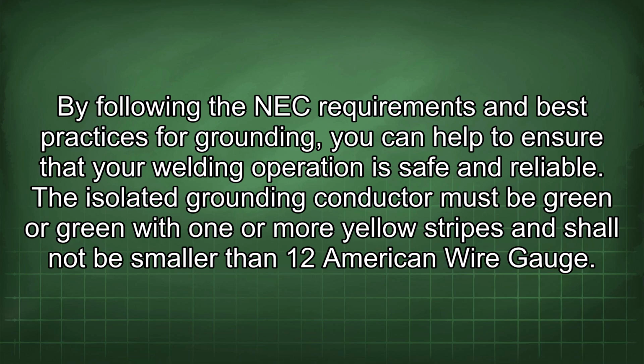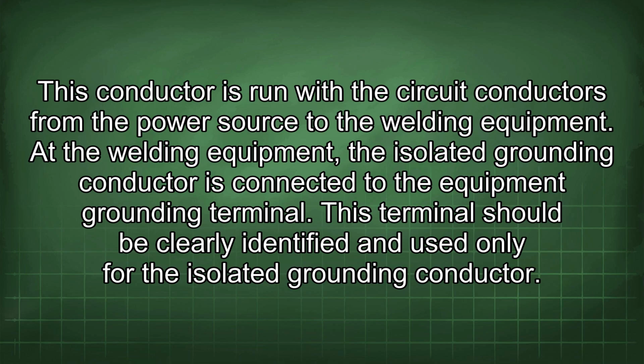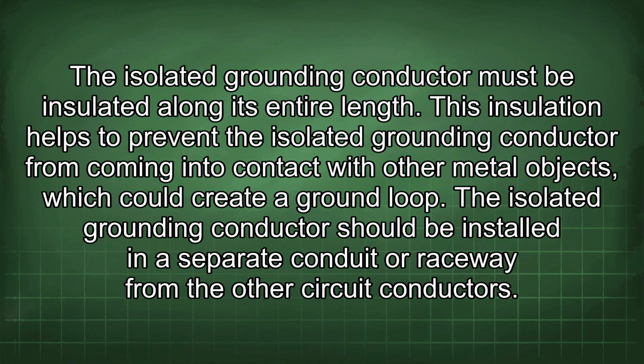safe and reliable. The isolated grounding conductor must be green or green with one or more yellow stripes and shall not be smaller than 12 American wire gauge. This conductor is run with the circuit conductors from the power source to the welding equipment. At the welding equipment, the isolated grounding conductor is connected to the equipment grounding terminal. This terminal should be clearly identified and used only for the isolated grounding conductor. The isolated grounding conductor must be insulated along its entire length.